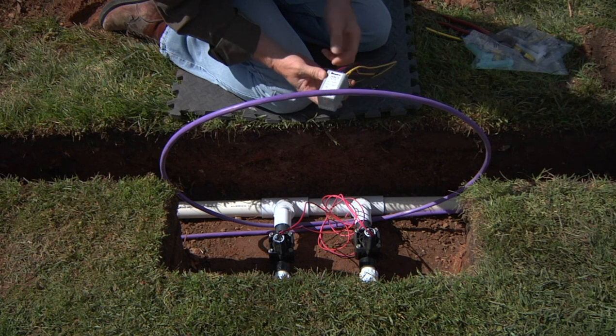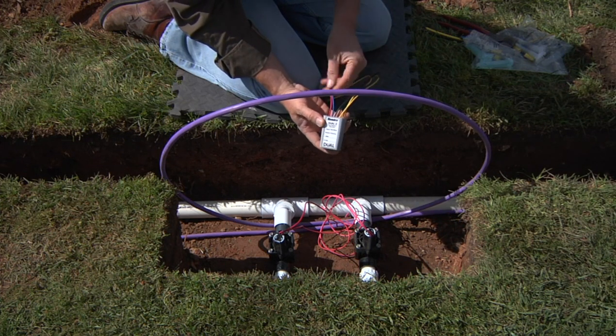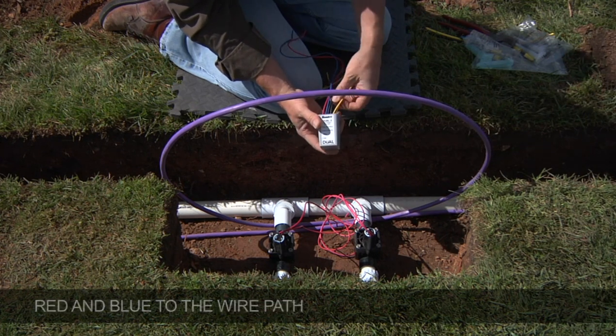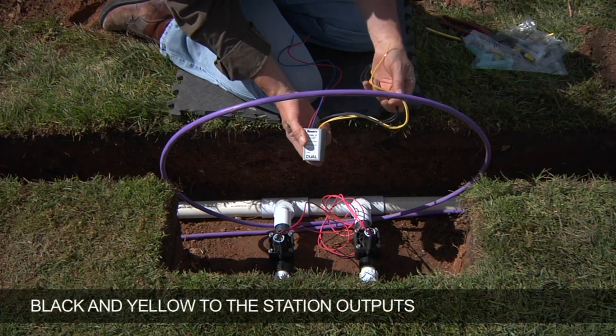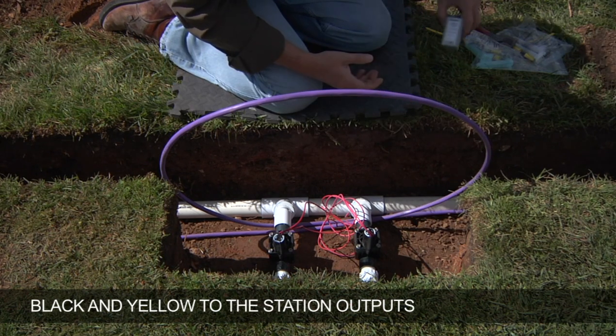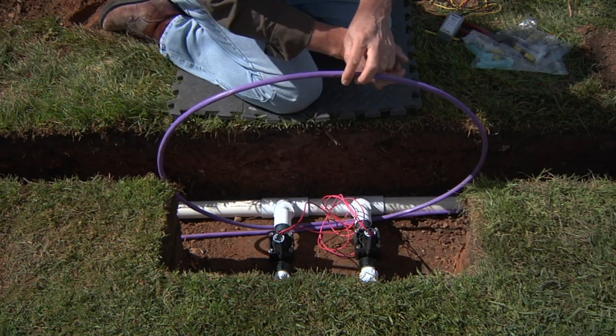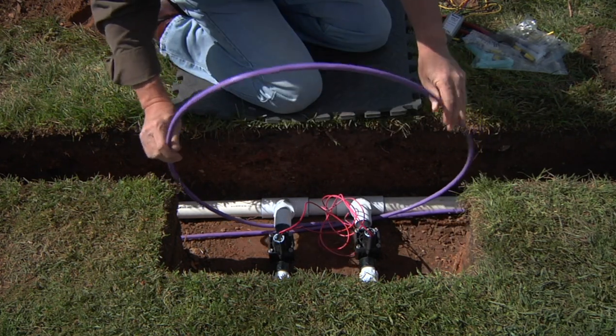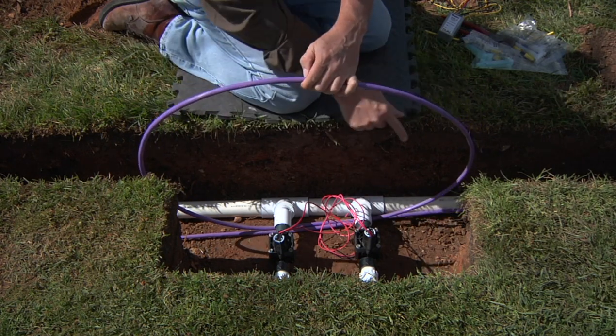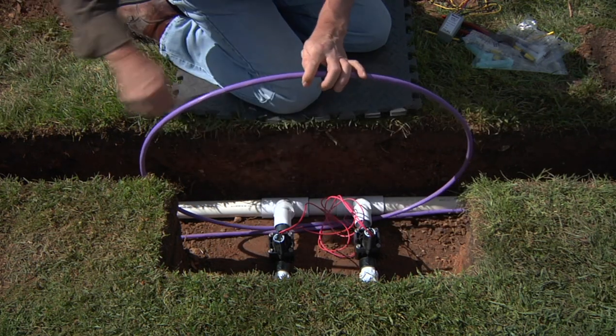Here we'll be installing a dual two-station output decoder. We have the red and blue wires that will attach to our wire path, and we have the two blacks and the two yellows which are the station outputs to the solenoids. You'll start by having the two-wire looped up for about 5 feet or about 1.5 meters of extra wire above ground to work with, and you can see that the two-wire comes into this valve box, loops up, and continues on downstream.